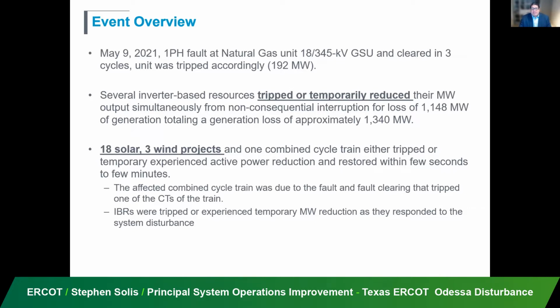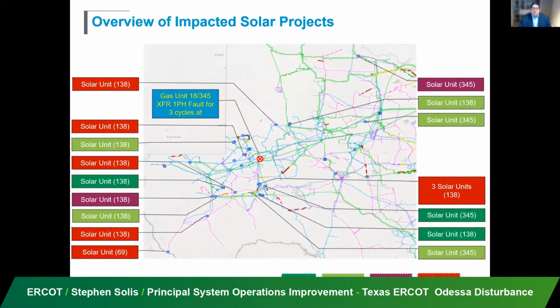In particular, 18 different solar sites and 3 wind sites saw a tripping of their inverters or a temporary reduction in megawatts in the order of about 1,148 megawatts of unexpected generation loss due to that disturbance. Because of that, we did see a frequency disturbance. We were able to recover rather quickly, but this was unexpected and caused some amount of alarm. When we look at the geographical dispersion of the impact of this disturbance, from that single fault, we saw solar units as far as 200 to 300 miles away, all across different kV levels, react negatively to that disturbance.